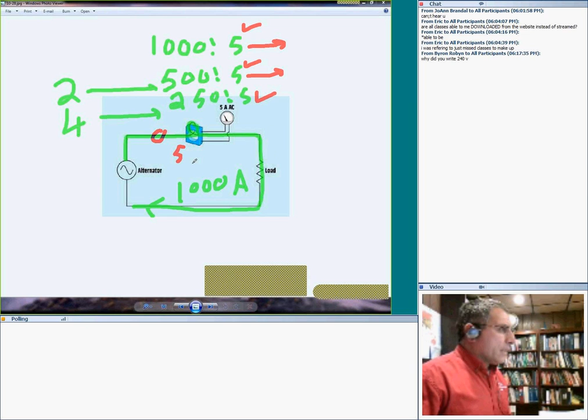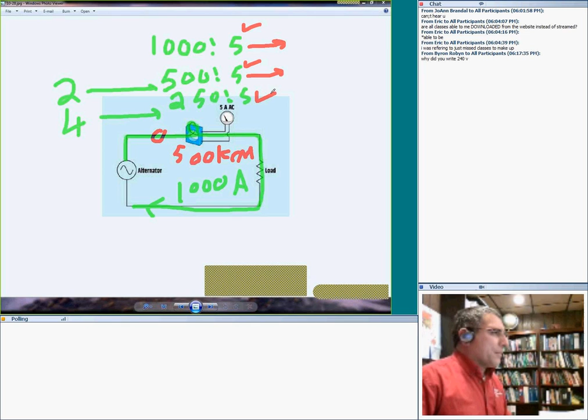So this looping method is for small conductors - number 8, number 4, number 6 if you're stretching it. You're not going to be able to loop a 500 kcmil conductor. But with a small conductor you can loop it a bit to increase the sensitivity of the CT.